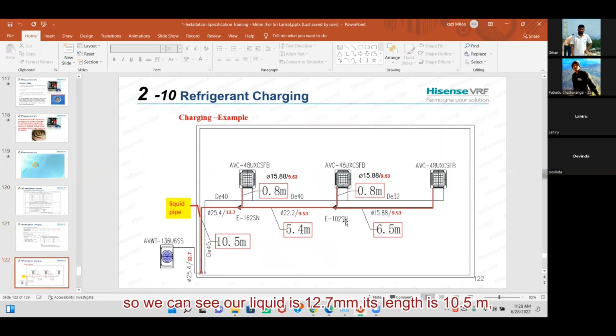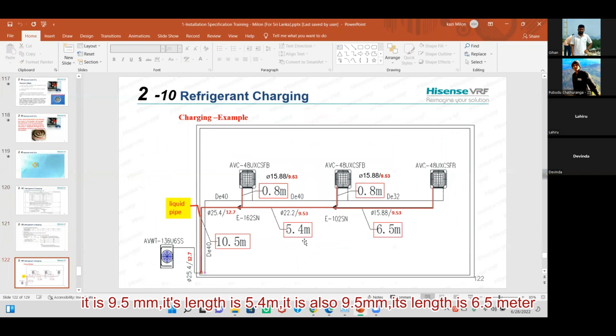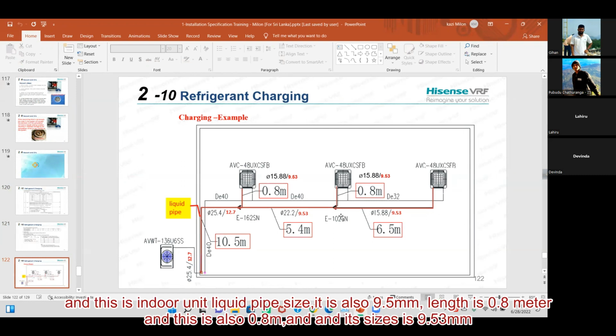Here we can see our liquid pipe is 12.7 mm. Its length is 10.5 meters. Here is 9.5 mm. Its length is 5.4 meters, and its length here is also 9.5 mm, its length is 6.5 meters, and this indoor unit's liquid pipe size is also 9.53. Its length is 0.8 meter, and its length is also 0.8 meter, and its size is 9.53 mm.